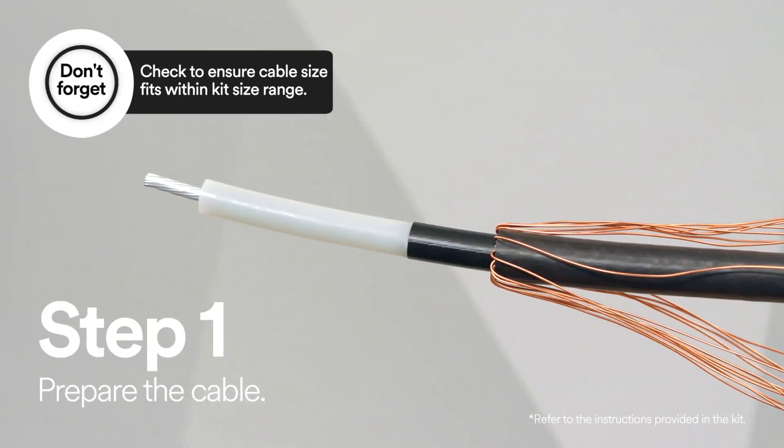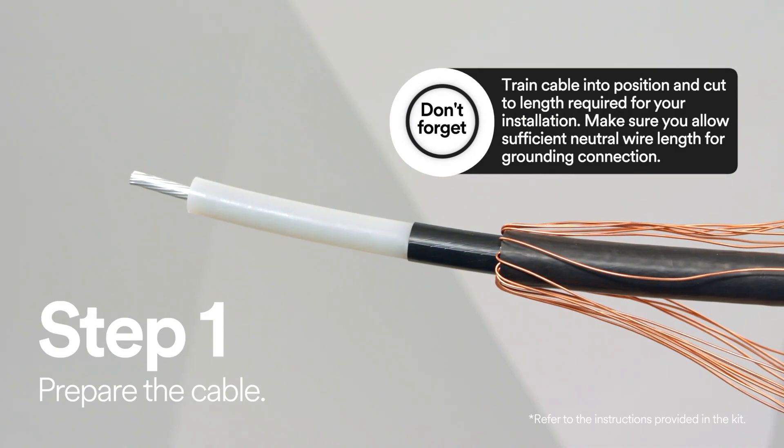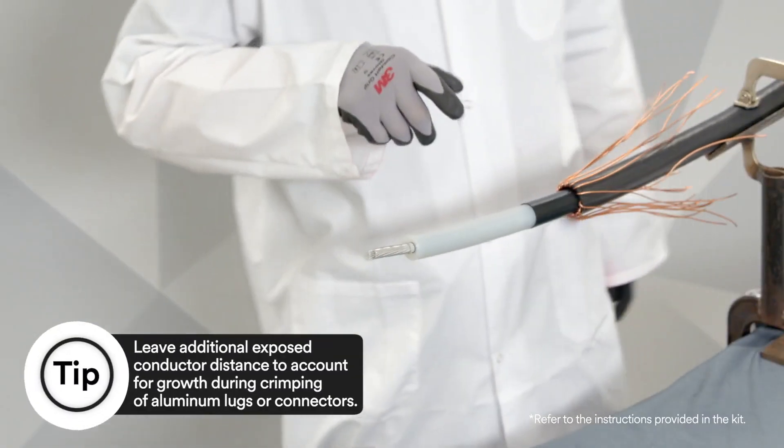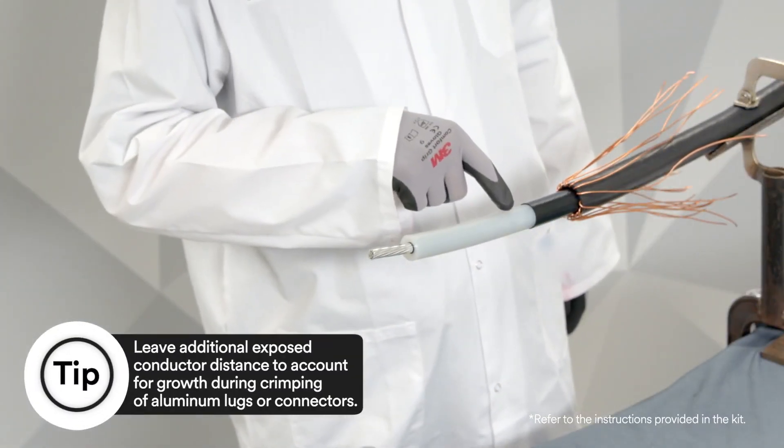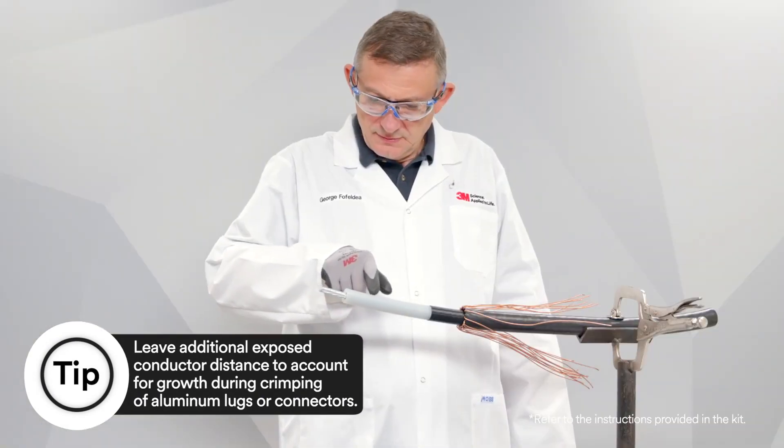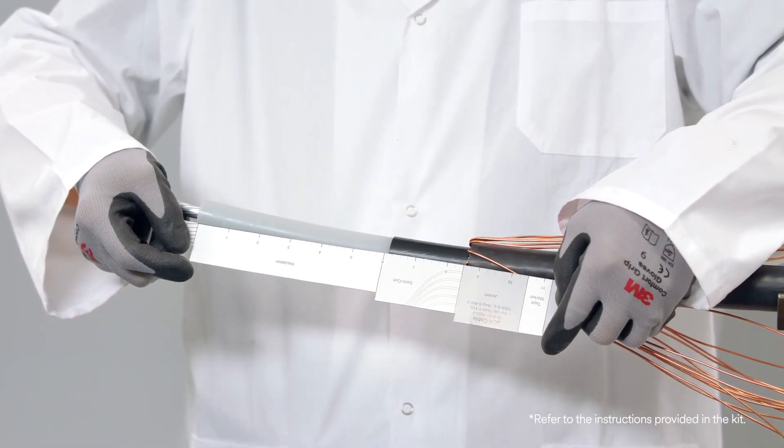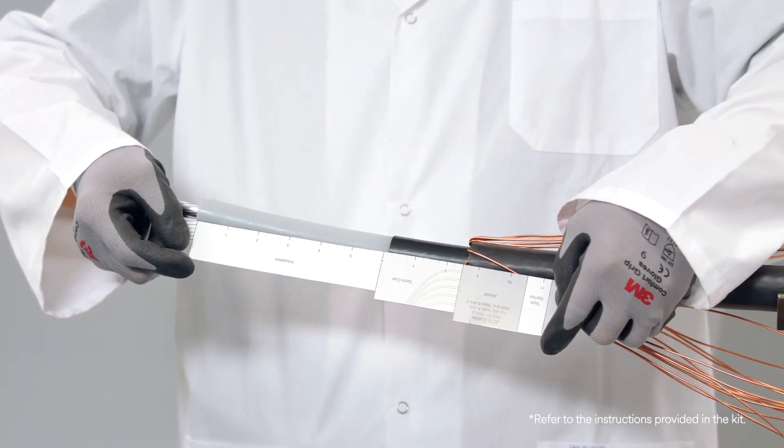The first and important step in the 3M Cold Shrink QT3 silicone rubber skirted termination install is to prepare the cable according to standard practices. It is important to make sure that you've removed all remnants of the semi-con layer, even if the semi-con layer comes off as one layer. You don't want to have any remaining black areas or particles on the cable insulation layer.